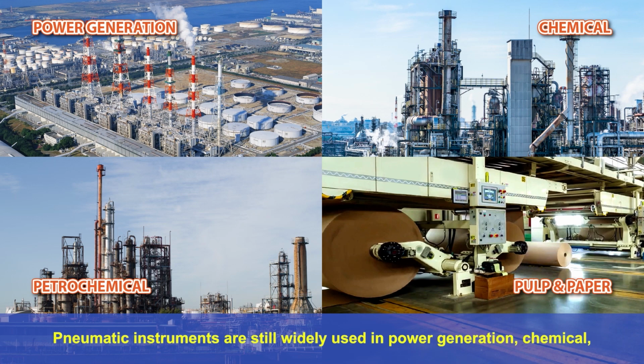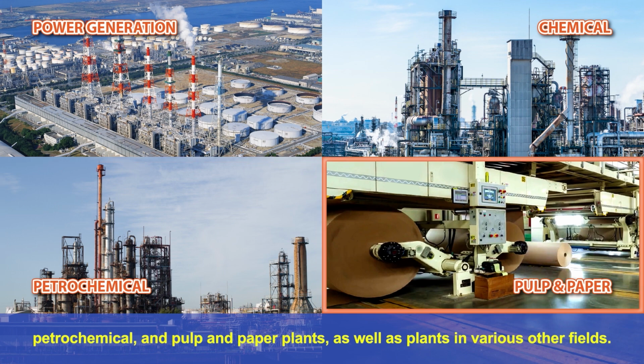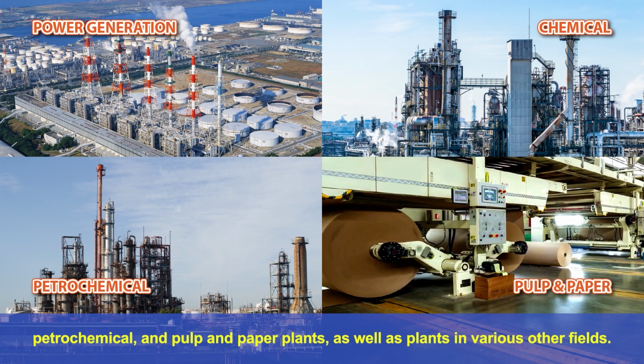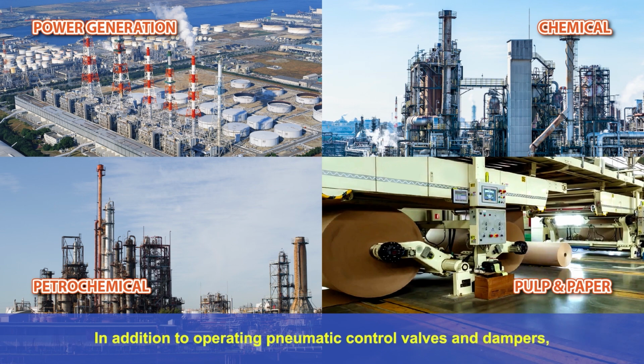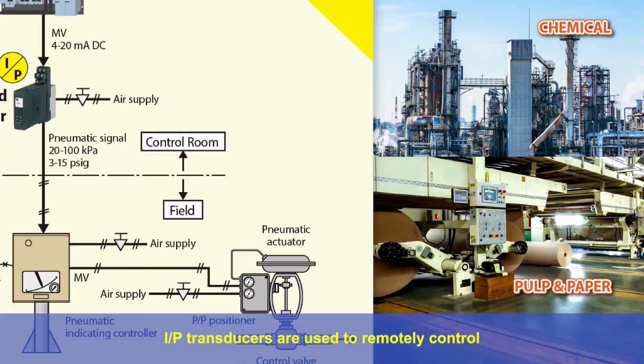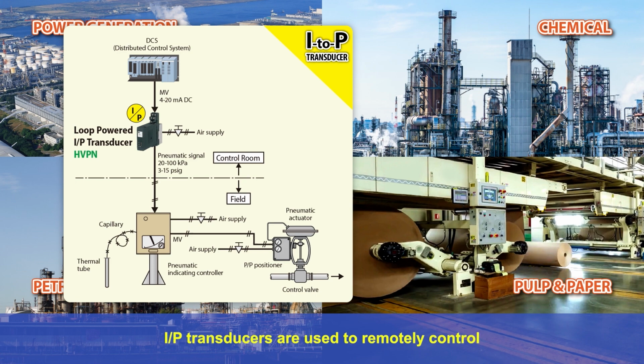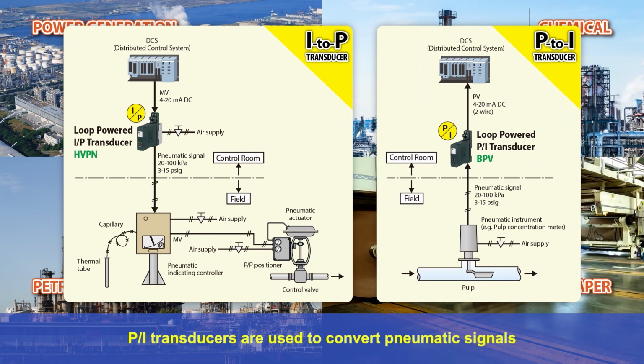Pneumatic instruments are still widely used in power generation, chemical, petrochemical, and pulp and paper plants, as well as plants in various other fields. In addition to operating pneumatic control valves and dampers, I-to-P transducers are used to remotely control pneumatic indicating controllers via a DCS. P-to-I transducers are used to convert pneumatic signals from old pneumatic field instruments into electrical signals that can be sent to a DCS. Use of I-to-P transducers and P-to-I transducers offer a cost-effective way to utilize existing assets in the field.